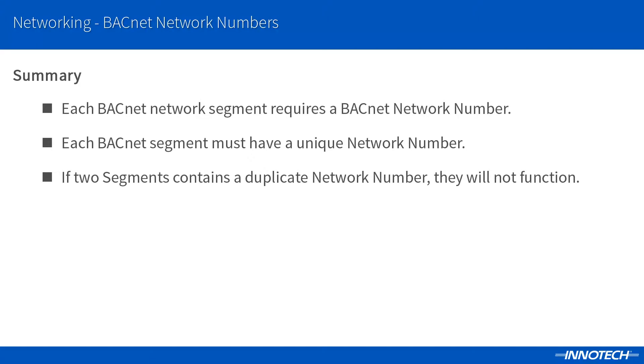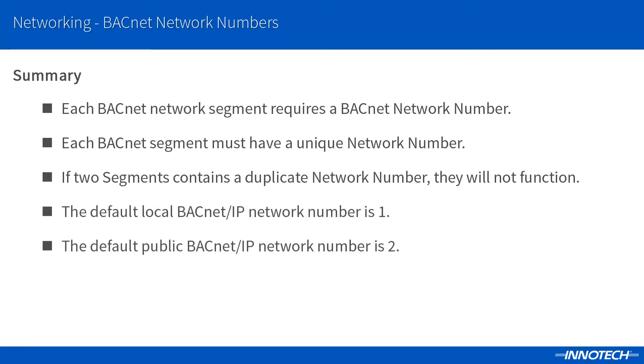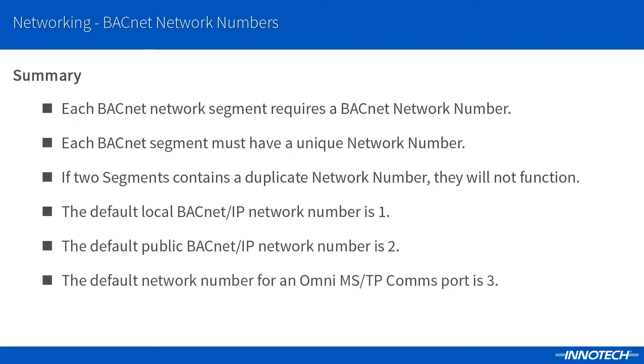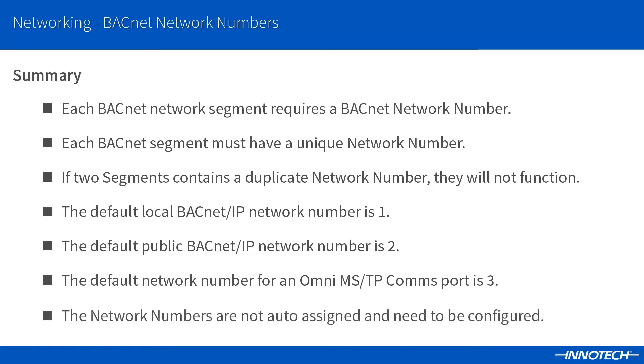In summary, each network segment must have a unique network number assigned. The local network number is 1 and the public network number is 2 by default. When an Omni comms port is configured as MSTP, it will default to network number 3. All network numbers are not auto-assigned other than the defaults and will need to be checked and adjusted when creating the networks to prevent duplicates.